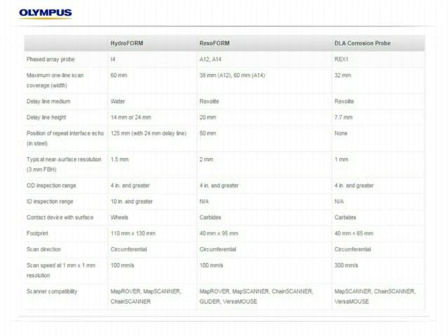Typically, the DLA, the way it's programmed and the way it works, does have the ability to usually scan at a much rapid speed. So you're looking at 100 millimeters per second for the Hydro-Rexo is very typical, and up to 300 is pretty typical for the DLA corrosion probe. Most of them are compatible with most of the scanner options as well. You just got to have the right configuration.